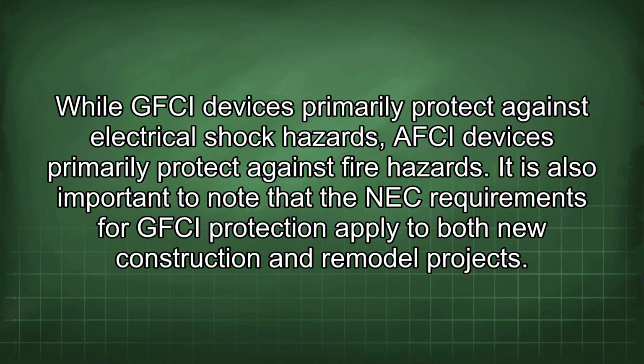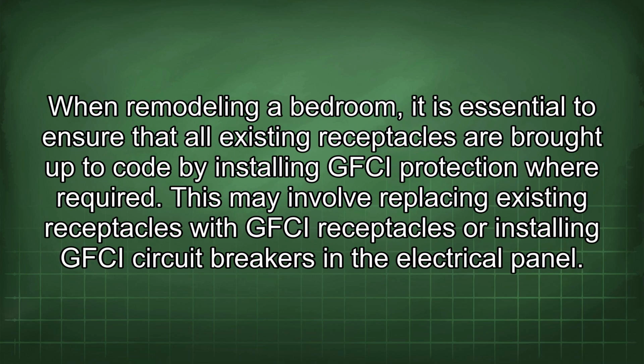It is also important to note that the NEC requirements for GFCI protection apply to both new construction and remodel projects. When remodeling a bedroom, it is essential to ensure that all existing receptacles are brought up to code by installing GFCI protection where required. This may involve replacing existing receptacles with GFCI receptacles or installing GFCI circuit breakers in the electrical panel.